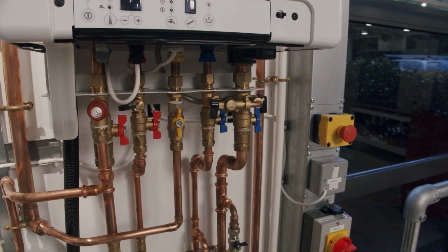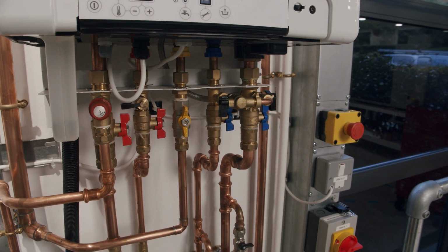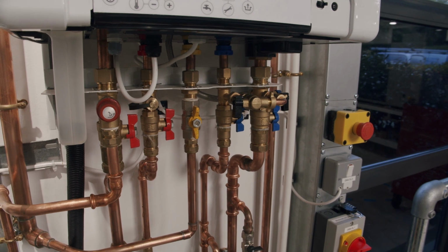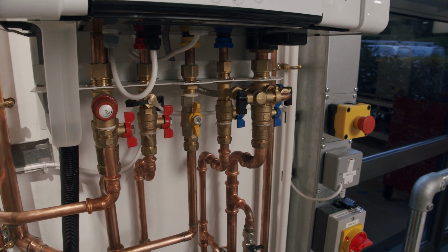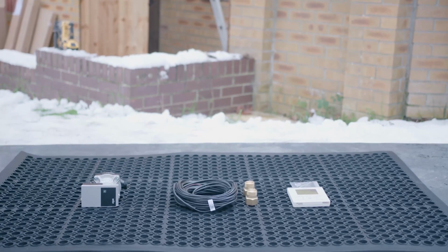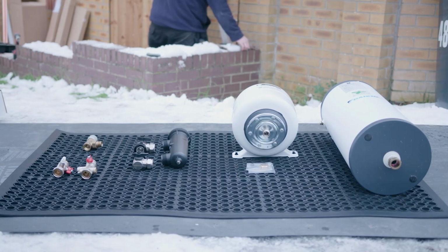The Daikin Altherma hybrid monobloc is plug and play, with all the main components already included. The primary circulation pump is contained within the boiler, circulating water through the heat pump, boiler and heating system. This pump is compatible with a range of pipe sizes and pipe lengths. The existing radiators and distribution pipework can be retained. For the installer, most of the essential components are supplied by Daikin. For the property owner, installation is faster, minimising disruption.